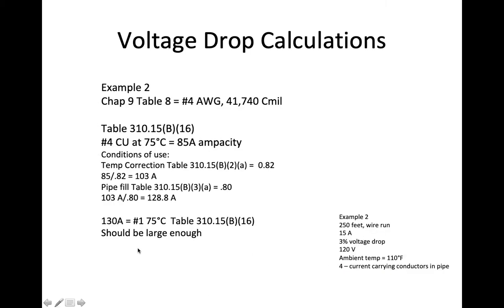Next up, I go to my table 310-15B-16 ampacity table, run my finger down the column to the 75 degree insulation column, and a number 4 copper conductor will handle 85 amps. So I need a conductor that can handle 85 amps to get 15 amps from point A to point B at this lower voltage.